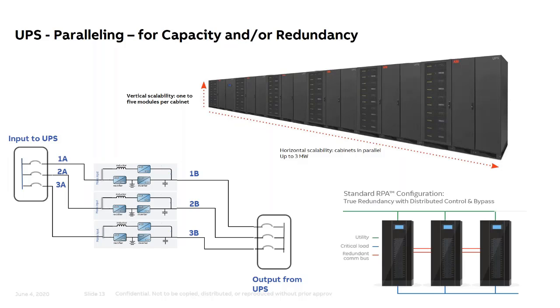Like the drawing in the lower left corner shows 3 UPSs. If we stick to 500 kW, 3 units in that configuration would support 1500 kW. But it could also be seen as 1 megawatt with N+1 redundancy. So most manufacturers can parallel UPSs. All ABB UPSs are parallelable. Typically, depending on the manufacturer, you can parallel 6 or 8 units. You hardly ever see that many, but technically it's possible.